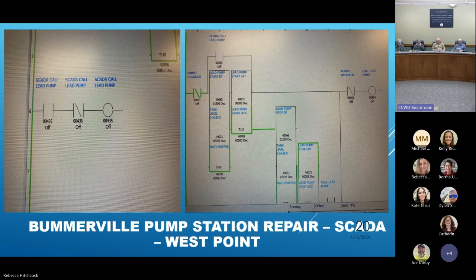This is what the ladder logic for SCADA looks like for a pump station. It's the kind of thing our electricians troubleshoot, like when a pump kicks on for a second and kicks off and the operator can't understand why. The electricians can get into the brain of the operation, and usually it's a lightning strike or some electrical glitch from the provided power.